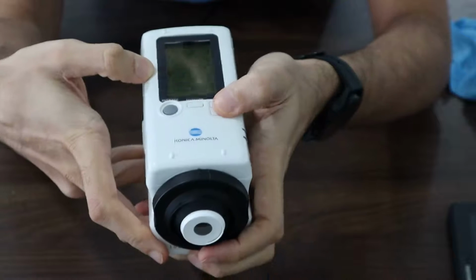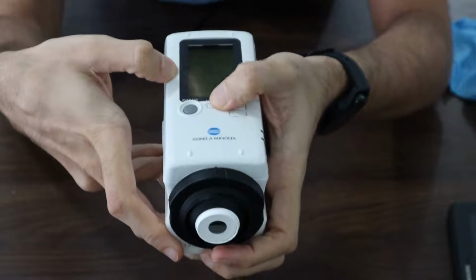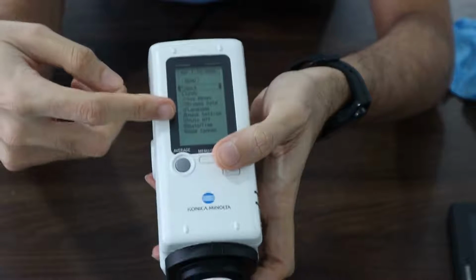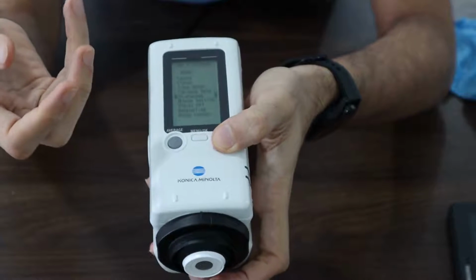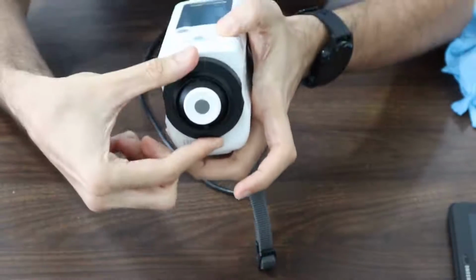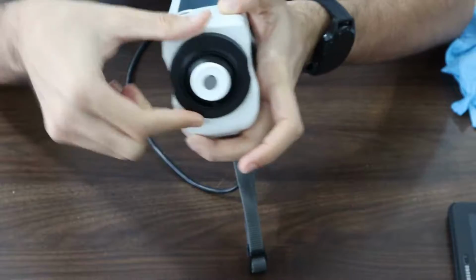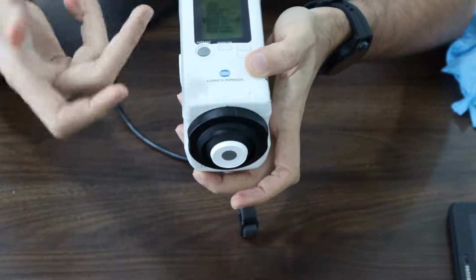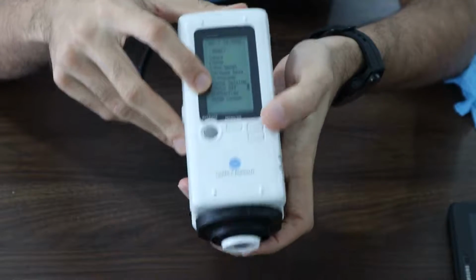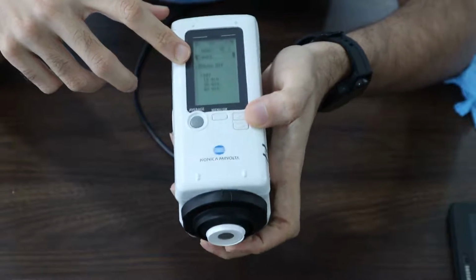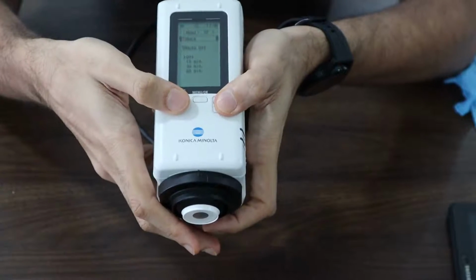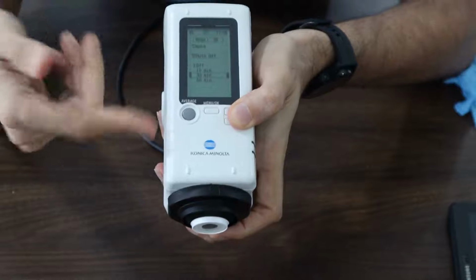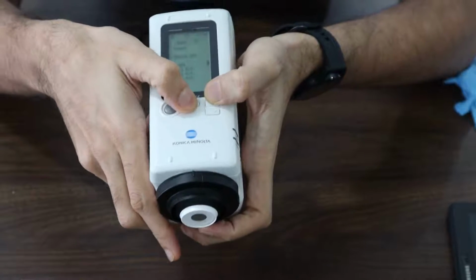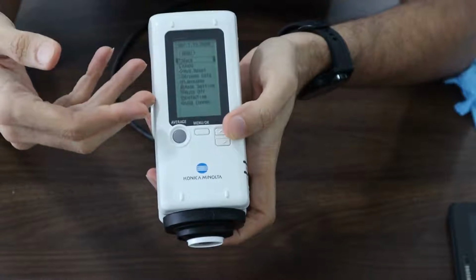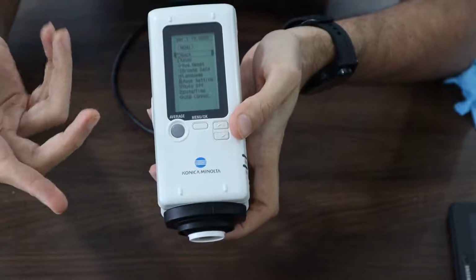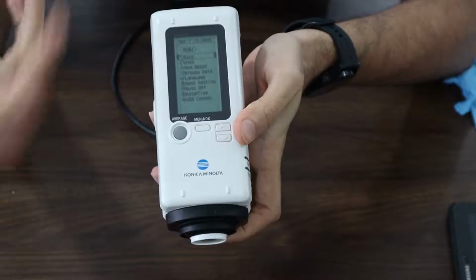Okay, the next is language selection, followed by mask setting. The language selection has been defaulted to English. The mask setting you do not have to change, because for a different model there was another attachment for this, but for the CR-20 there's only one mask setting, so this is not a useful function. There's an auto off function here, which by default is set to no auto off, but you could set it to 10 minutes, 30 minutes or 60 minutes. Okay, this would be useful especially if you're running on battery. For example, you don't want to leave it turned on and forget to switch it off, and then after you come back the battery is completely depleted.